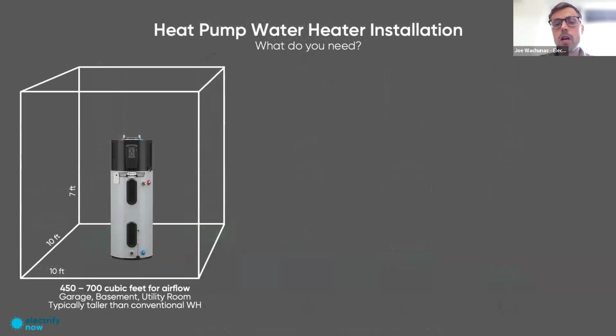You need some airspace for that heat pump water heater to breathe, to pull that warmth out of the air. Depending on the manufacturer, they recommend between 400 and 700 cubic feet of air for your water heater to breathe. If your water heater is located in a garage or basement, that's typically more than enough air.